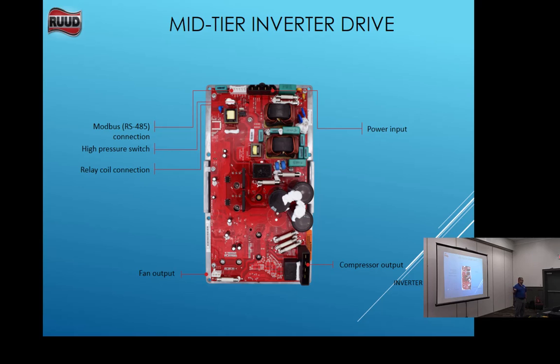Okay, something happened somewhere. This is where we have our high pressure switch up here. Our Modbus cable runs from here. The controls run from here over here to our control board that tells the inverter drive what to do. Our compressor outputs here, our inputs here. This board is really hard to diagnose. Okay, I'm gonna go through it.